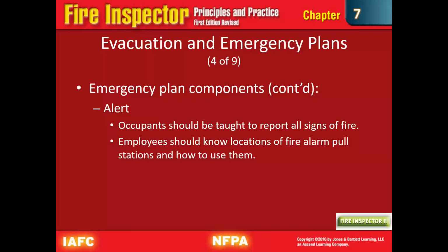This is something I've run into. There was a school that I was working with that completely retrofitted the entire campus with fire alarm systems, and that was great. That was amazing. Well, they were worried about the students tampering with the pull stations, so then they put a tamper box over the pull station. Well, this tamper box, if you pull it, it will sound an alarm. And it's not like your normal fire alarm, it's just kind of like a loud, annoying buzzing, but it's there.